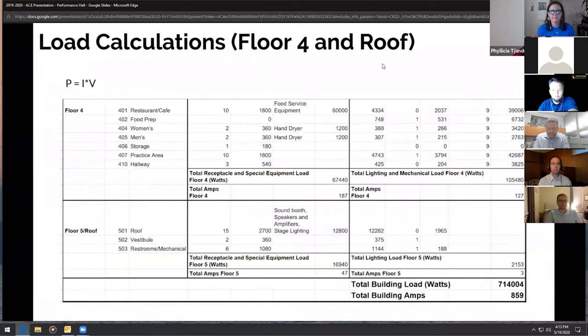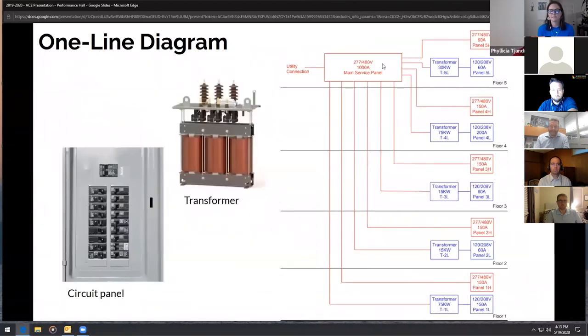We repeated the load calculation process for floor 4 and the roof. Then we used the information from the load calculations to create a one-line diagram, which shows the power flow of the building's electrical system. We showed how many amps are needed to support the loads on each floor and how we have separate panels for different voltages. They all feed to the main service panel, which is 277-480 volts to support both voltages of panels, and also showed how we need transformers for the 120-208 volt panels so they can be compatible with the larger voltage of the main service panel. On the left are example pictures of what a circuit panel and transformer might look like.